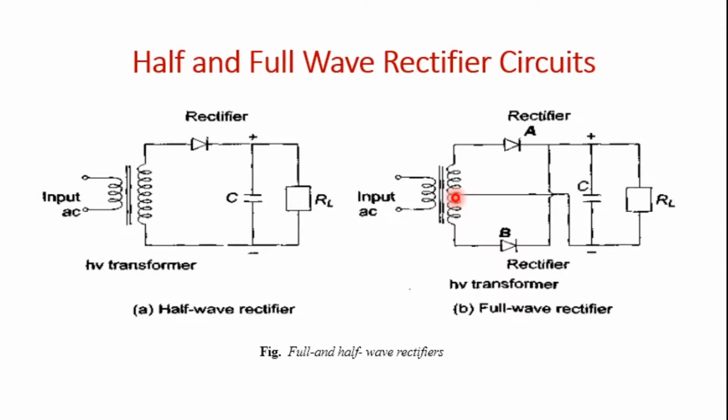Apart from the filament, the cathode and the anode, they contain a protective shield or a grid around the filament and the cathode. In modern high voltage laboratories and testing installations, semiconductor rectifier stacks are commonly used for production of DC voltages. Semiconductor diodes are not true valves since they have finite but very small conduction in the backward direction.